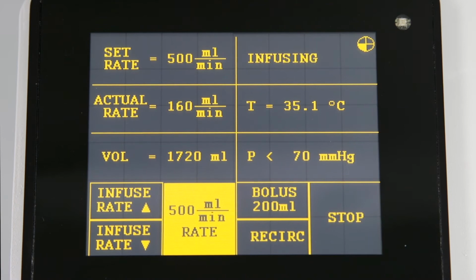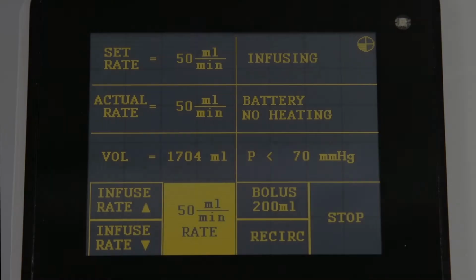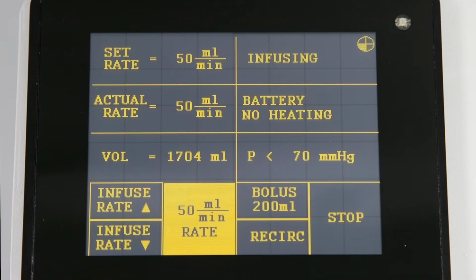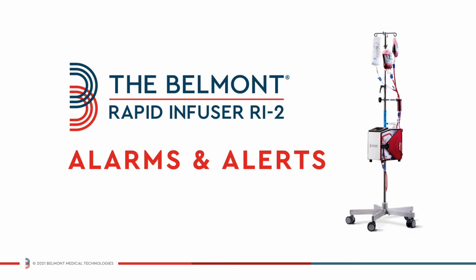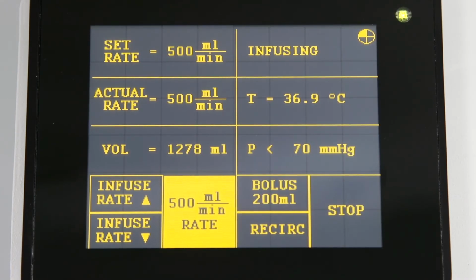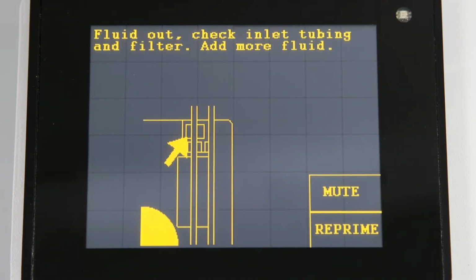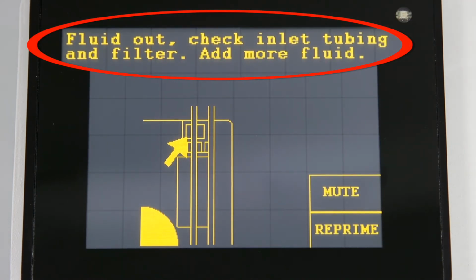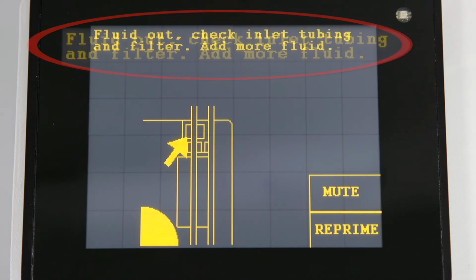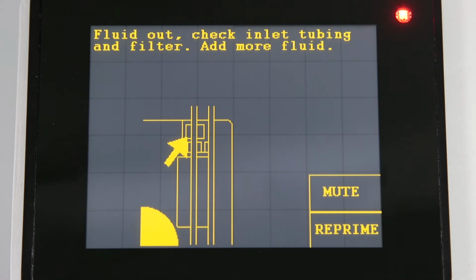The battery is charged when the device is plugged in. A fully charged battery can provide infusion at the maximum allowed 50 milliliters per minute flow rate for up to 30 minutes. The Belmont Rapid Infuser RI-2 will alert the user with an audible alarm if it senses a problem, and will display instructions for corrective measures. To silence the alarm and return to normal operation, simply follow the instructions on the display.